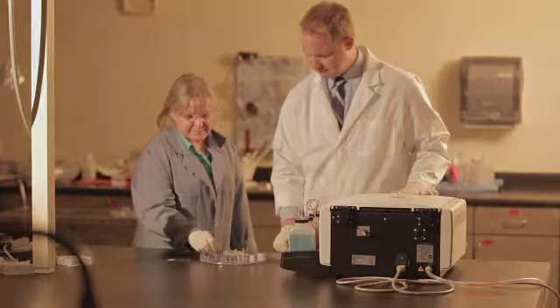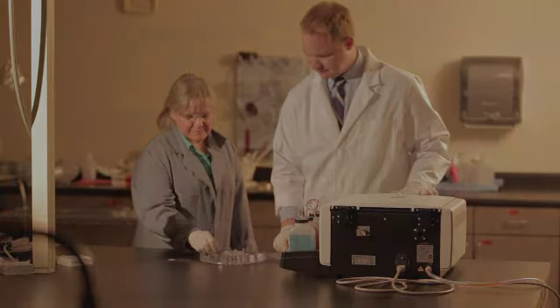Now that the stainer has been properly set up and slides have been stained, it is time to cover some of the key preventive maintenance steps that are the same for each model. Preventive maintenance is necessary in order to ensure long-term satisfaction of the stainer. Preventive maintenance consists of daily, weekly, and monthly maintenance. PM charts are provided for each model to help each user keep track of the maintenance performed. These charts are necessary to meet some accreditation standards depending on the laboratory.